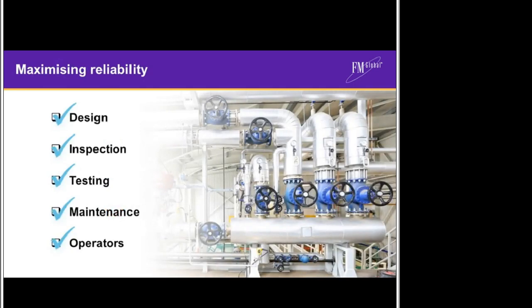Maximizing the reliability of any device is a function of five elements. Design is incredibly important because it will impact everything that follows. There are two outcomes that make for a well-designed turbine safety device: repeatable, reliable operation, and the ability to prove repeatable, reliable operation whilst the turbine is in service. If a safety device cannot be proven whilst the machine is in service, it is of limited use. Unfortunately, the specter of value engineering looms large. Well-intentioned but naive cost optimization during the design phase often has dramatic effects on operational resilience.